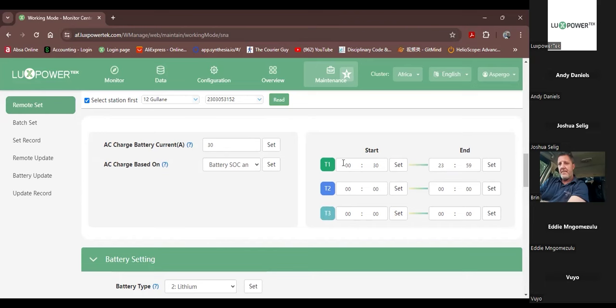For instance, I might want to say that I want to charge the battery between 1 a.m. and 2 a.m., then between 8 a.m. and 10 a.m., and then again from 6 p.m. to 8 p.m. So that's the only time that you're going to use all three time settings, if you have three different time zones that you're going to set in. Otherwise, if you're doing it for 24 hours, like this machine that's got no PV, then we will set it for 24 hours here. All right.